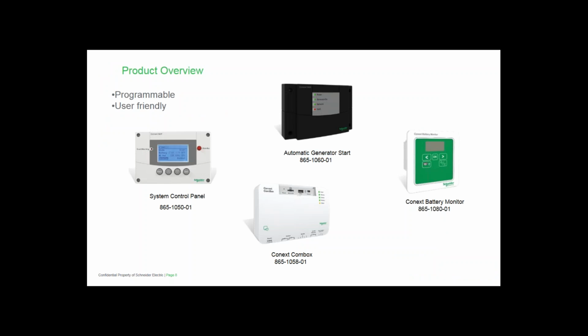The system control panel allows user programming of all XW devices in the network. The automatic generator start can be programmed for any one of 14 different generator types. Start triggers are voltage, load, and state of charge percentage, which requires the battery monitor. The battery monitor provides an accurate account of battery statistics. We should also mention that the battery monitor state of charge percentage can be used to trigger the auxiliary port.